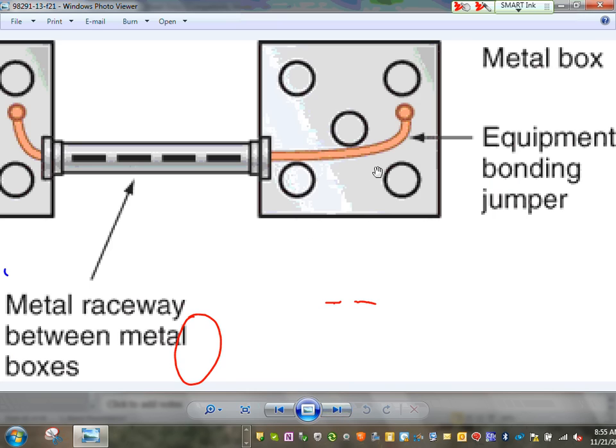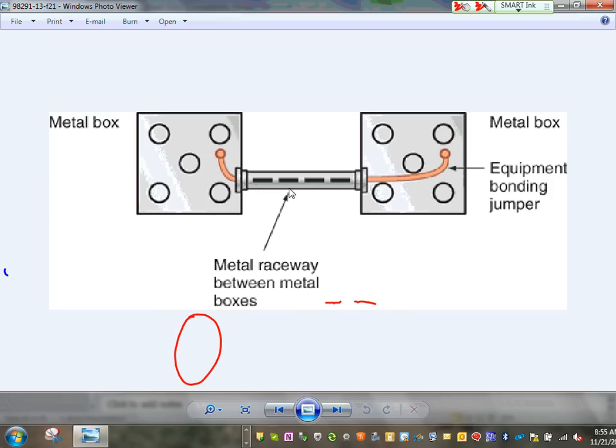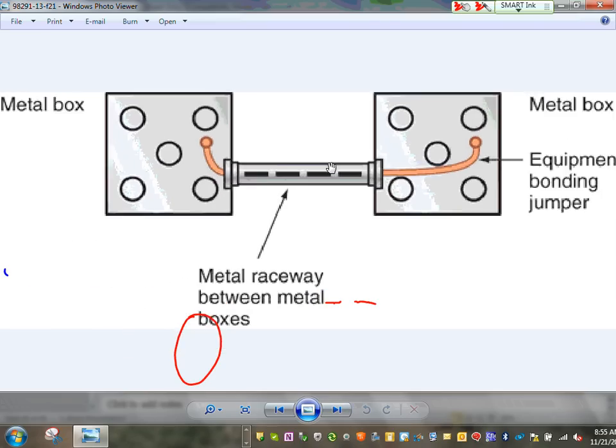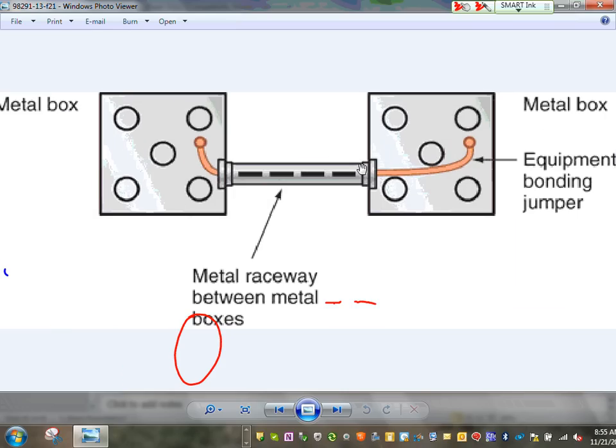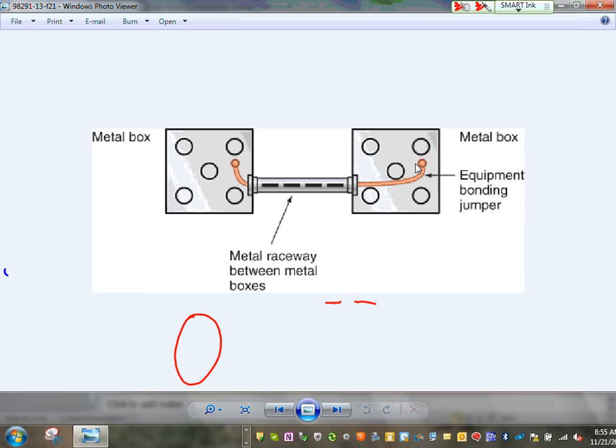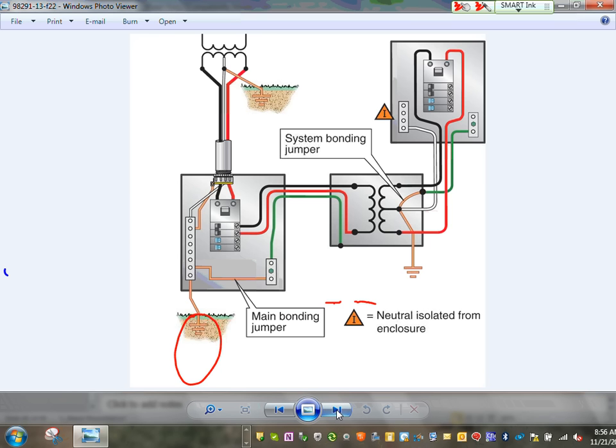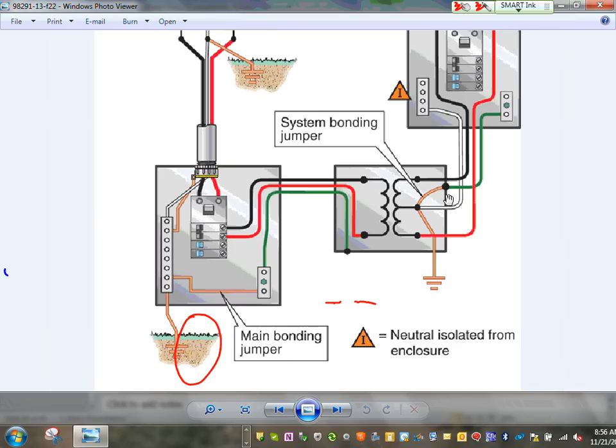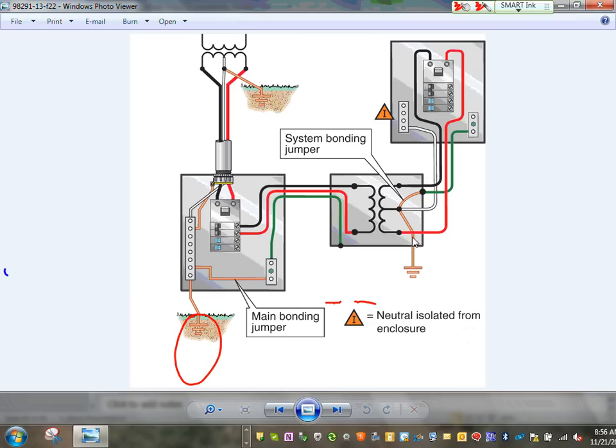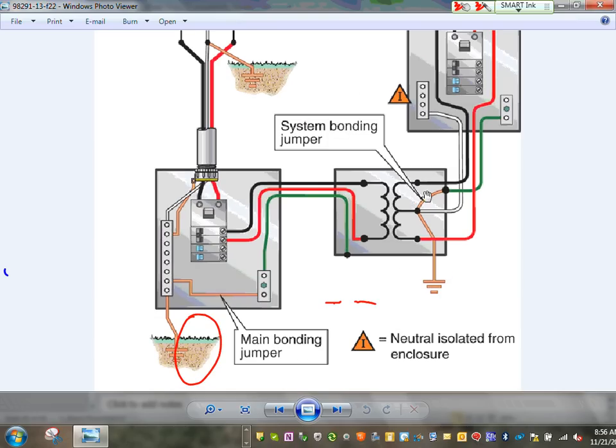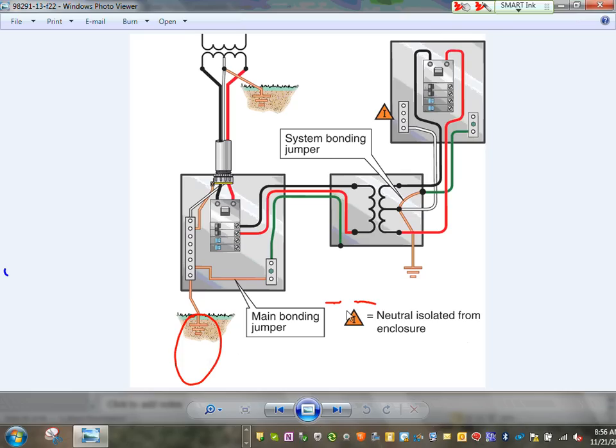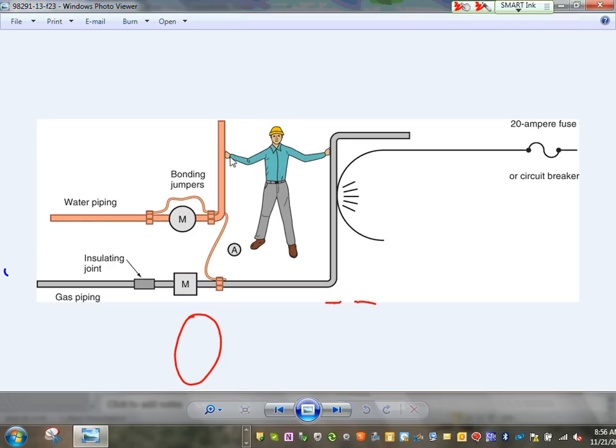This is bonding boxes together. If these are metal raceways between metal boxes, the connectors here will bond you. If these are non-metallic raceways, you have to have an equipment bonding jumper between the two. System bonding jumper, Adam, we call it the system bonding jumper, taking the neutral and bonding it to the enclosure of the service disconnect means or the transformer that you own and operate. In this case, if it's a system, it's right at the transformer that you own and operate. The reason why we bond, we told you guys, is because if this becomes energized on one side and you touch both sides, that current can go right through your heart and it will send you to join the Lord so fast.